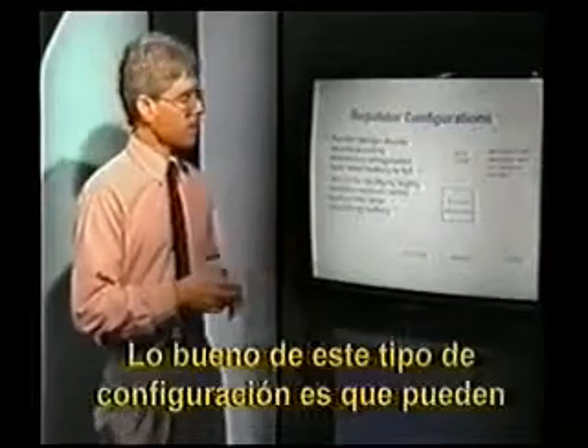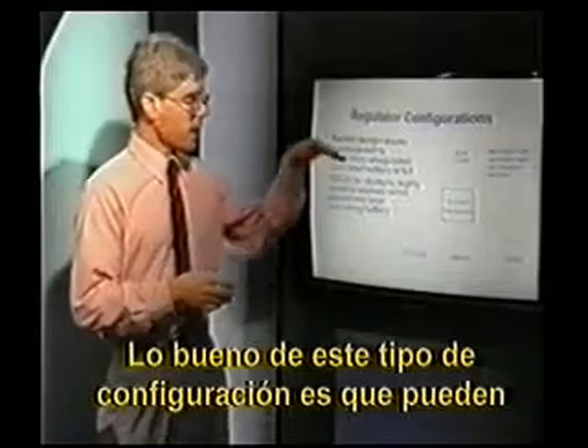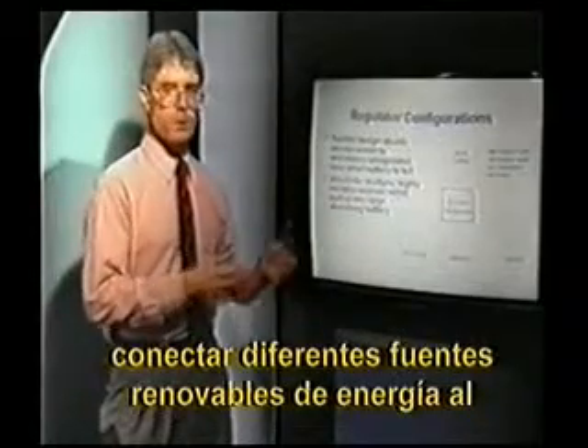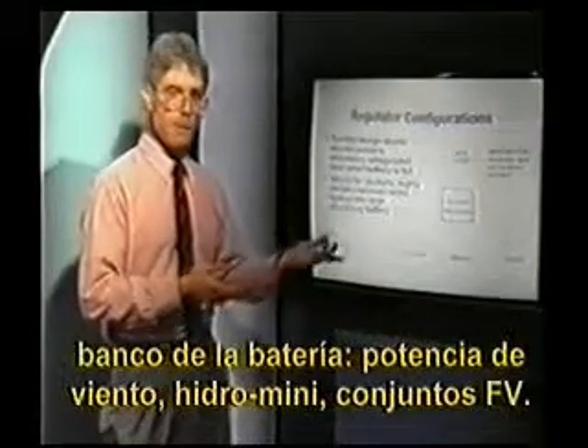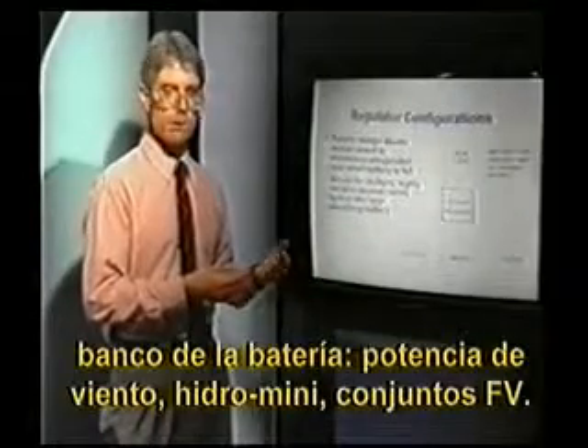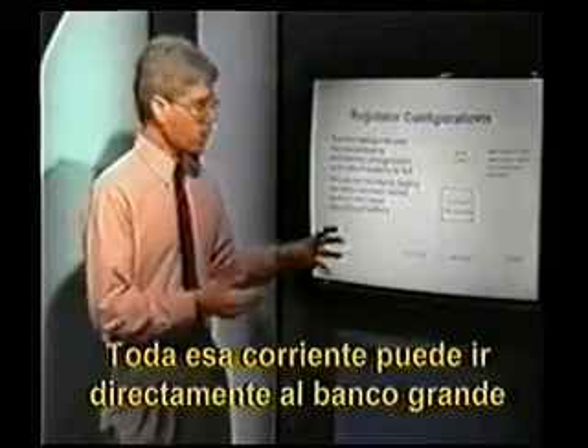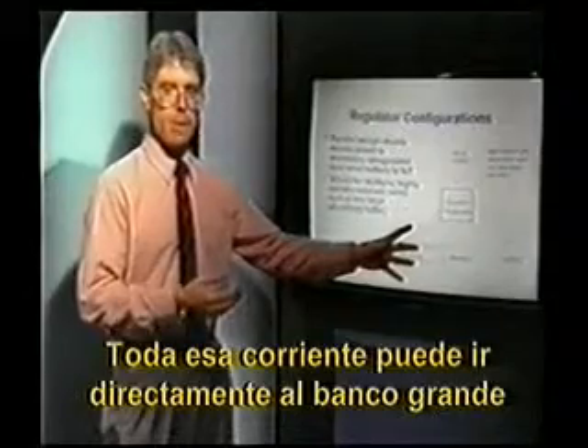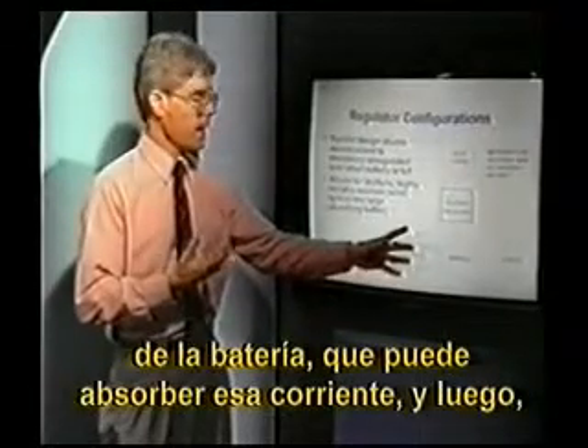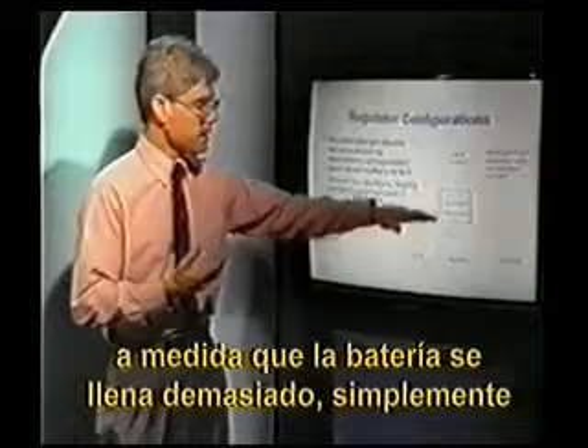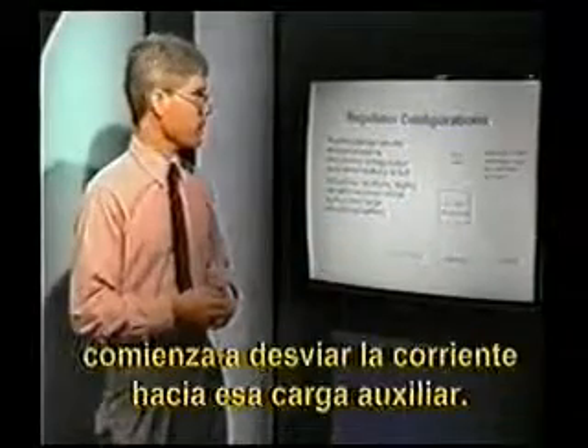The nice thing about this type of configuration is that you can connect a number of different renewable energy sources to your battery bank. Wind power, mini hydro, photovoltaic arrays. All of that current can go directly into the large battery bank, which can absorb that current. And then as the battery gets too full, it simply begins to divert current away to that auxiliary load.